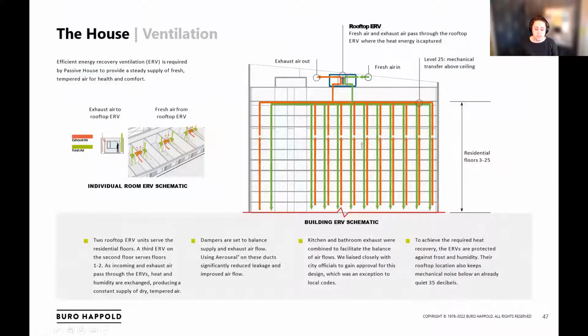The ventilation system, adding on to the heating and cooling system, was designed again to maximize the energy recovery gained through an energy recovery ventilator. We also studied a floor-by-floor approach versus a whole building approach, and for this system we ended up using the whole building approach.